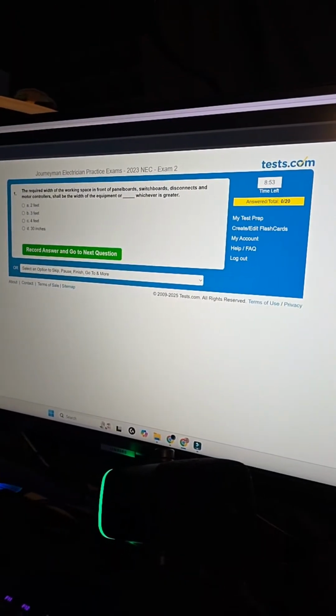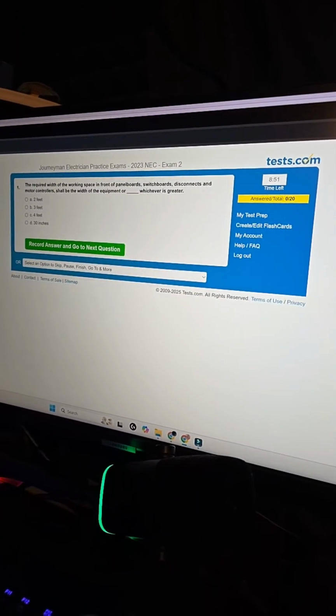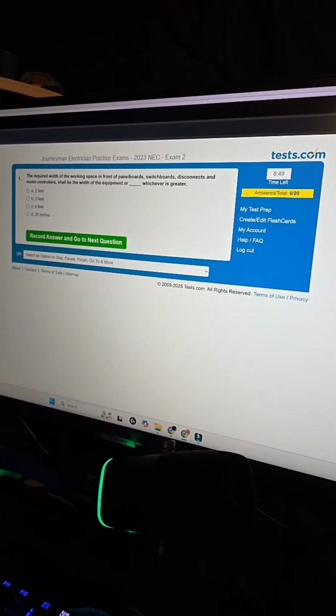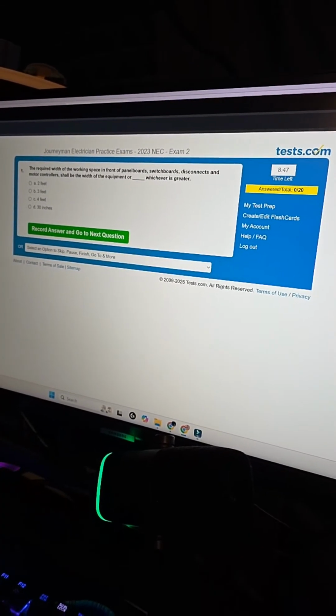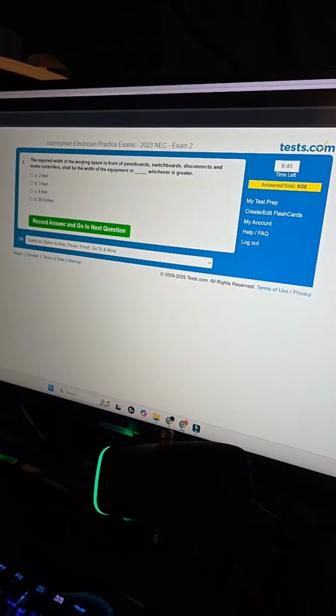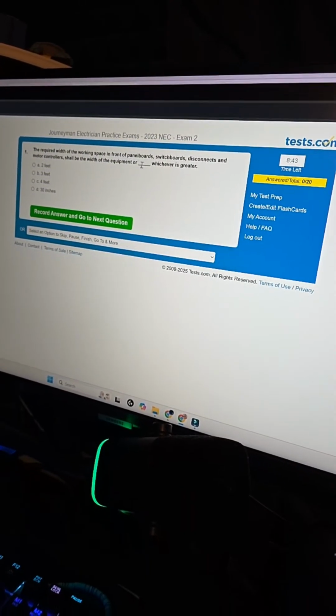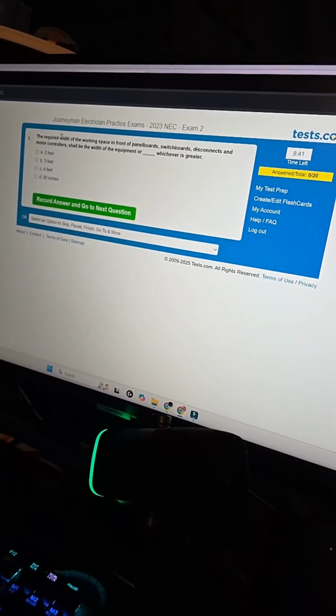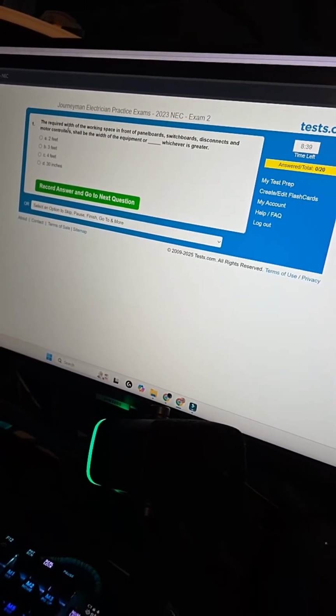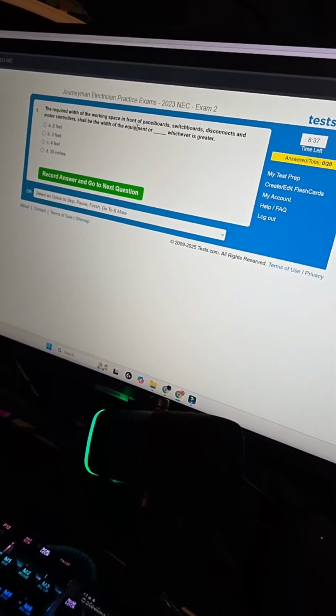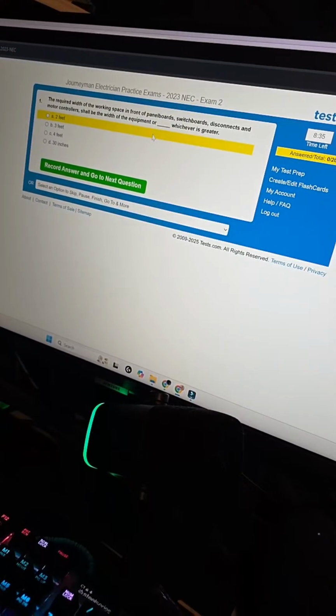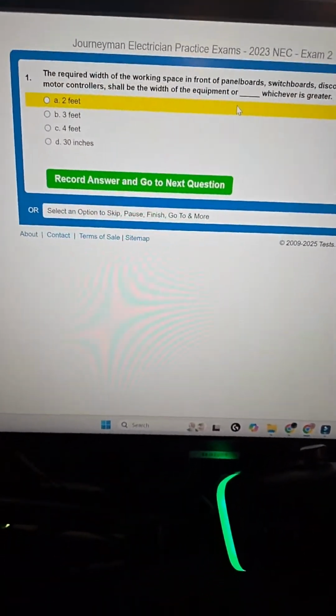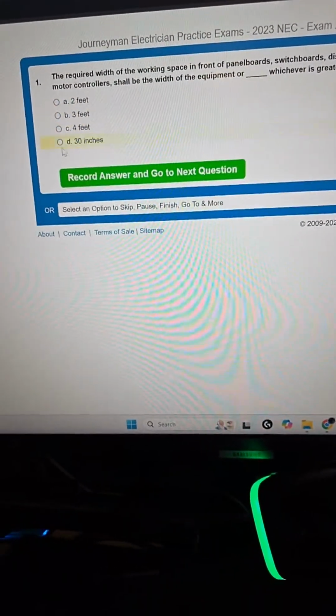So you'll have to forgive my tripod for moving so much. Here we go. All right. So required feet front to back. It says the width of the equipment, or the required width of working space. It should be 30 inches. The width is 30 inches. 36 would be front to back. So we're going to go with 30 inches because that's going to be the width.